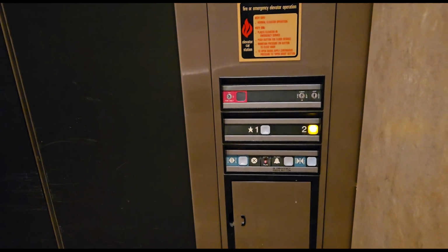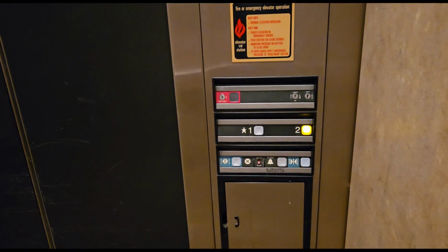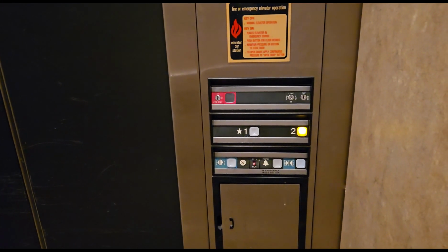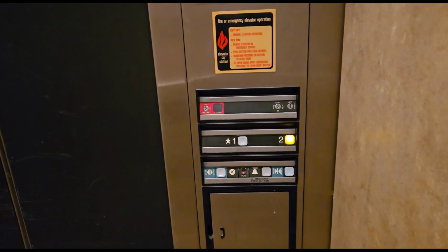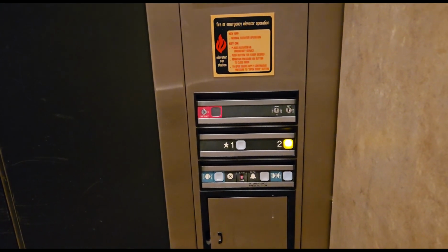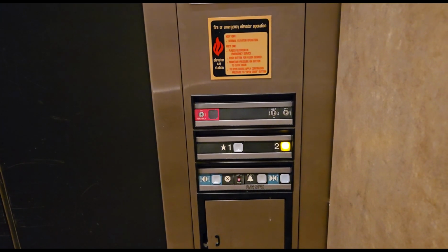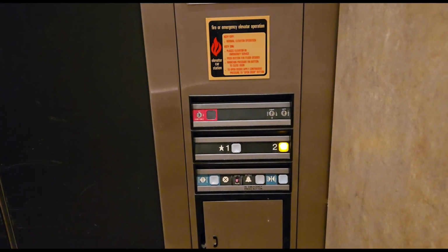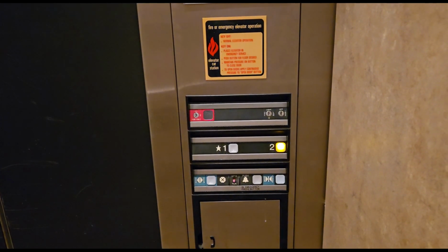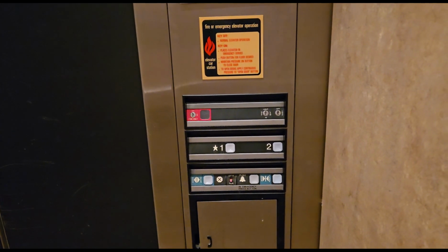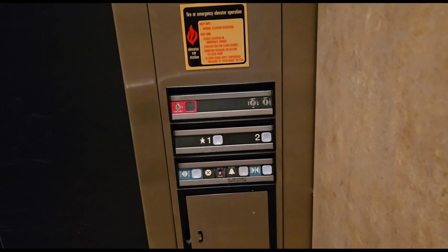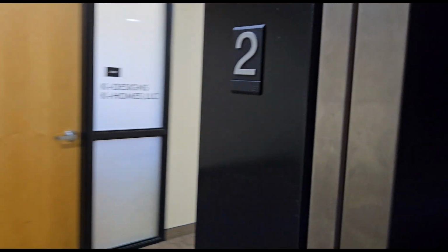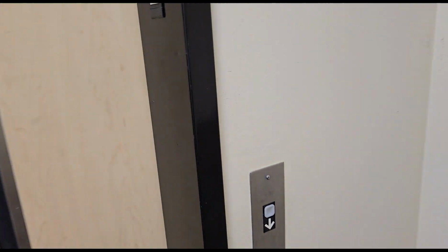Would always recommend doing these things with an elevator technician if possible. Even if your client does not schedule them with you to do the elevator testing, and they just give you a key and they say, good luck. But so far so good. So we recalled it and killed the power. Then we reset it, flipped the power back on and bypass key back on. And now we're in it. Now we're on floor 2. So that's how you do the elevator recall.